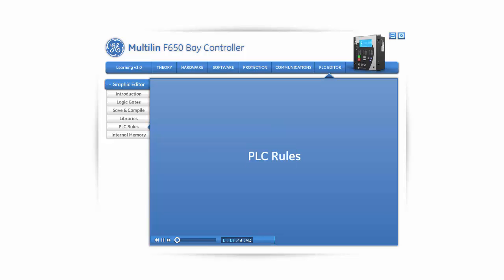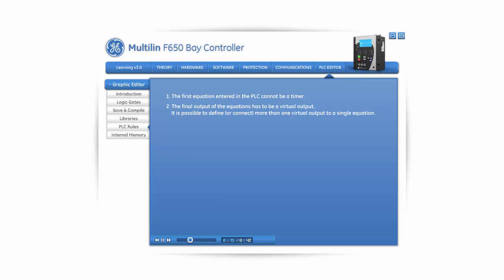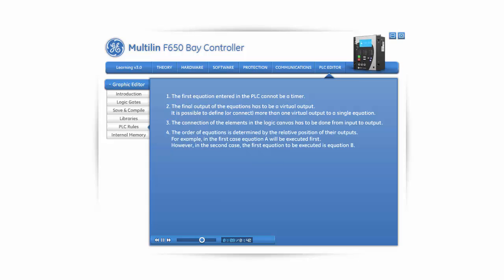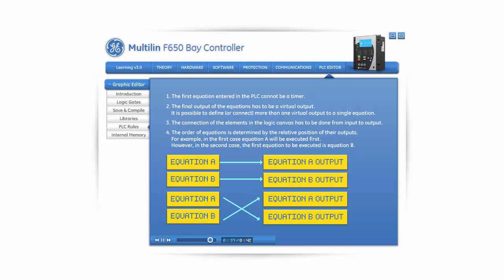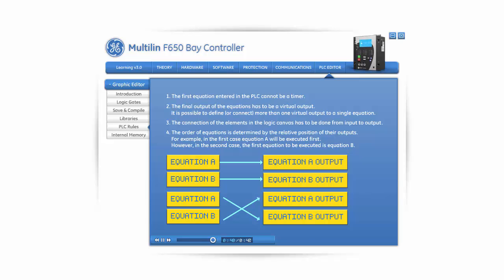Now that we have learned how to create logic, it's important to mention certain rules to follow in order to create correct logic. The first equation entered in the PLC cannot be a timer. The final output of the equations has to be a virtual output. It is possible to connect more than one virtual output to a single equation. The connection of the elements in the logic canvas has to be done from input to output. The order of equations is determined by the relative position of their outputs — for example, if equation A's output is positioned first, it will be executed first, but if equation B's output is positioned first, then equation B will be executed first.